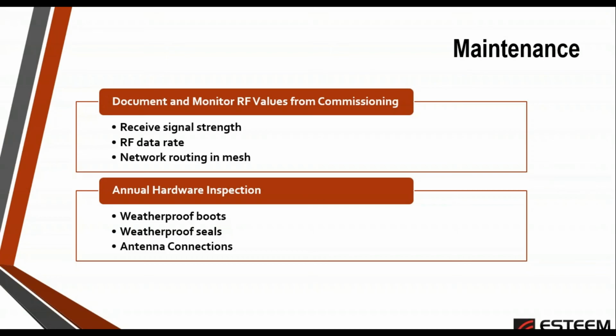When the radios are first put in, we need to make sure each communication link into every radio has its current signal strength marked down. Because if in the future there are communication problems, the first thing maintenance, troubleshooting, or support will ask is, what is the current signal strength? If it's a -80, that number by itself doesn't tell us much.